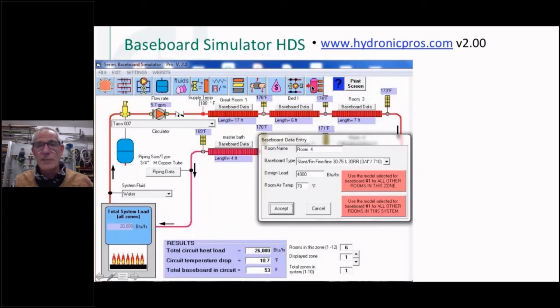So I can pick a certain size of tank, put an operating condition on that tank, and it'll tell me what my run time, my boiler on and off time would be. So this is the baseboard simulator. And so what you do here is I can pick a pump. I think I put a Taco 007 in here. I put a supply temperature of 180 degrees going out to this, just a small fin tube circuit. I don't know, about a 20,000 BTU load. And so I can go in there and I can define, there's a pull down menu. I can put Slant/Fin in there, Embassy, whatever type of baseboard you want, different sizes of baseboard, different models of it. And then I put the load in up here.